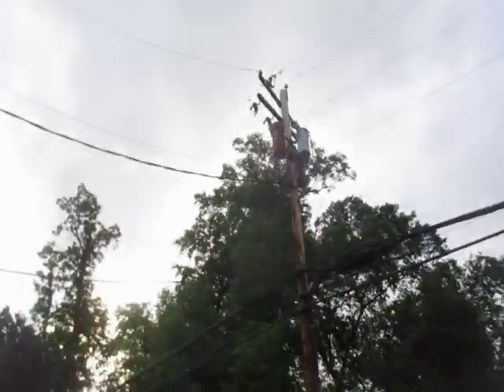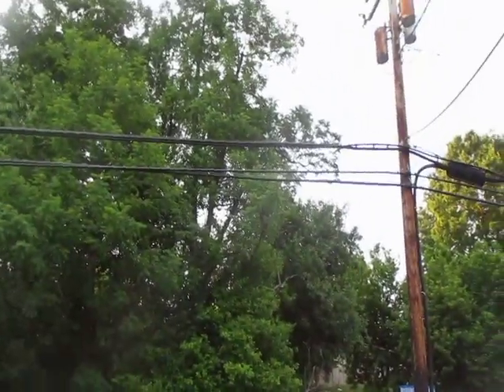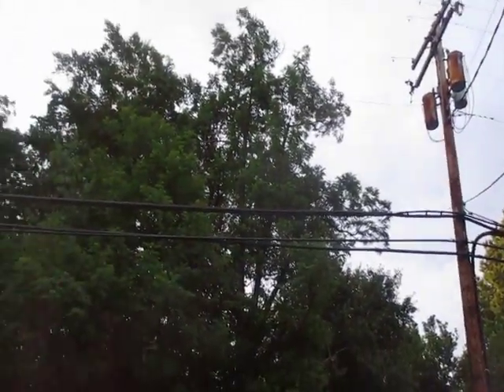We got some rusted 15 kVA transformers up there. Got some silicone fuses. So let's see what we got. We have an open delta connection. That's limited 3-phase for the garage there. And we have a single phase 120/240 with a pulled fuse.